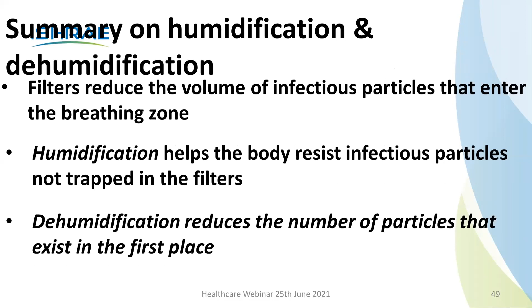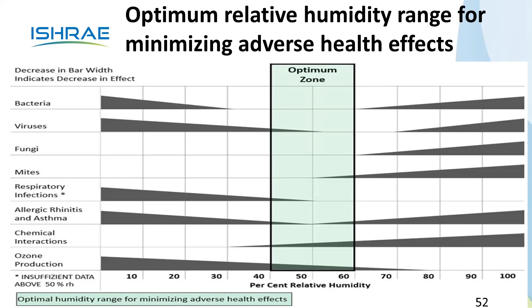If you see this particular chart, it is called the Sterling chart, and it is from ASHRAE. You see the thick lines, they represent more growth. As the lines become thin, the growth is less. So if you see bacteria, at very low RH there is very high growth. As you go towards 40% RH, it is reducing. All those pathogens, the growth reduces as you go towards 40% RH. Again, from 60% onwards, towards 100%, the growth is increasing. So the optimum zone for any healthcare facility is considered to be 40 to 60% RH.